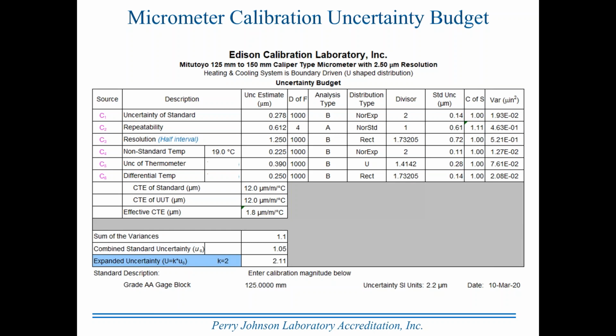Consequently, a scope might say that the micrometers can be calibrated from, well, let's say 1 millimeter to 125 millimeters. So they would have, in essence, a 0 to 25 millimeter, a 25 to 50, 50 to 75, 75 to 100, 100 to 125. They could calibrate those 5 micrometer ranges. Now, if you take an individual micrometer and calibrate it toward the low end of its measurement capability, down around 1 millimeter, for which you would have a standard, I should say, and then you calibrate it at the high end at 25 millimeters, you can develop what's called a relative uncertainty statement, which is the uncertainty expressed in terms of a variable, and in dimensional, the variable would be length.